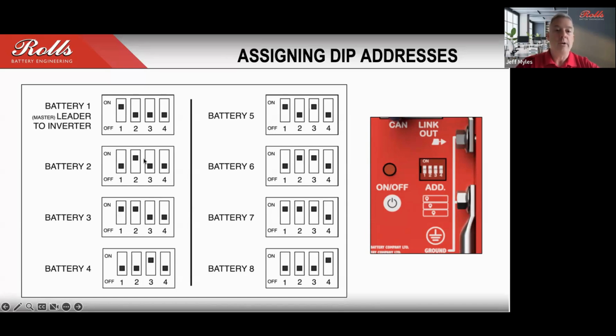That primary battery is going to be the one that's connected to the inverter. Whether you're connecting with the CAN bus port or the RS-485 port, in either case you're always going to connect that to the bottom battery in the stack. Then all of the corresponding batteries will be connected. Battery 2 will be the next one in the stack, and so on. Then the link in, link out port cable will be connected from battery to battery as you move up the stack.